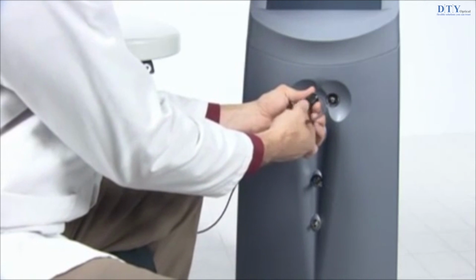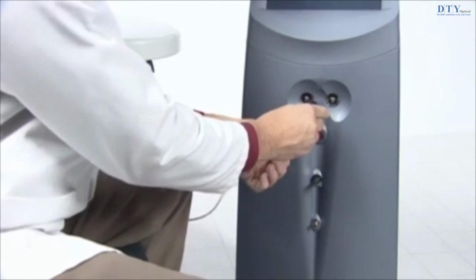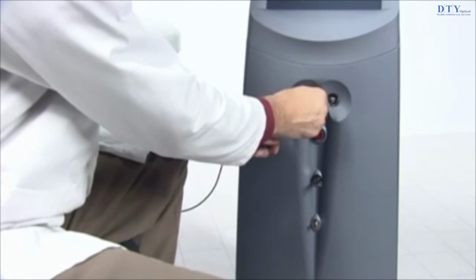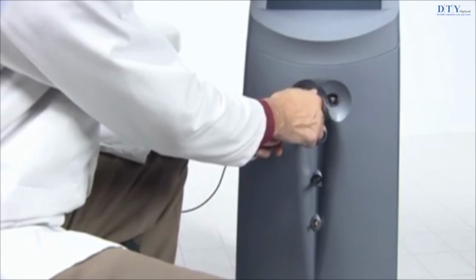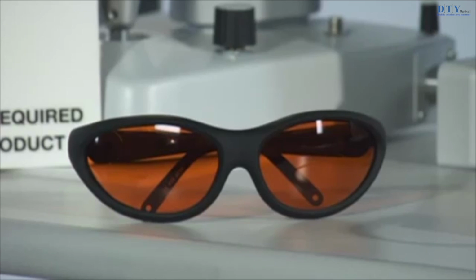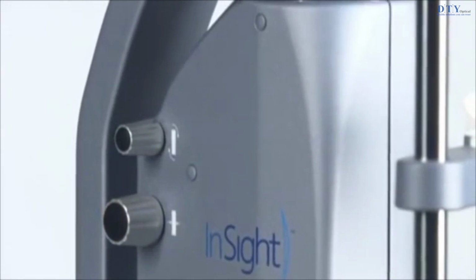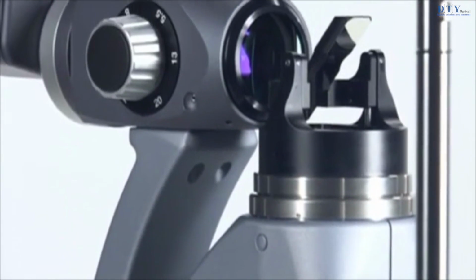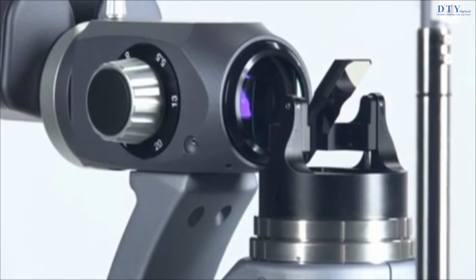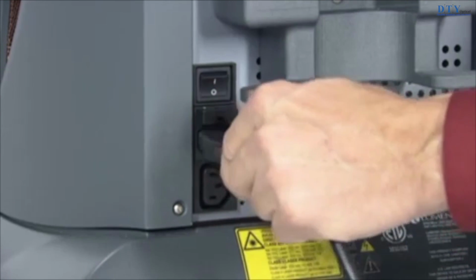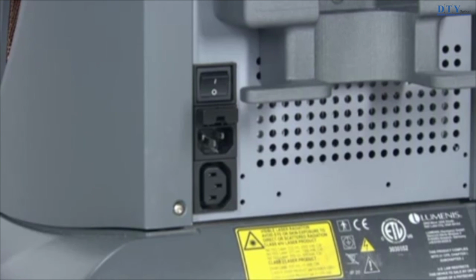Remember these safety tips. Always make sure the delivery device is properly connected to the laser. Improper connection can result in a dangerous inadvertent secondary laser beam, resulting in severe eye or tissue damage. Never substitute prescription eyewear for the appropriate laser safety eyewear. Prescription eyewear can concentrate the laser light to the eye. It might also be shattered by a high power density beam, possibly causing severe eye damage. Never look directly into any optical lens, optical fiber, probe, or laser system aperture while the laser is energized. Severe eye damage could occur. Make sure the laser is completely shut down before inspecting any delivery system or laser components.